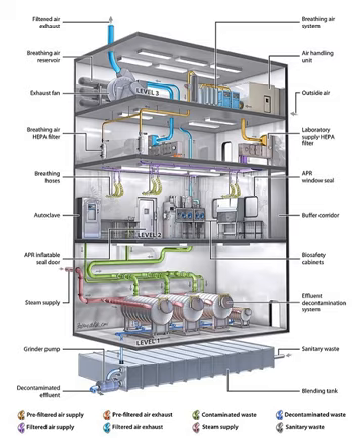In addition, the facility which houses the BSL-3 laboratory must have certain features to ensure appropriate containment. The entrance to the laboratory must be separated from areas of the building with unrestricted traffic flow. Additionally, the laboratory must be behind two sets of self-closing doors to reduce the risk of aerosols escaping. The construction of the laboratory is such that it can be easily cleaned. Carpets are not permitted, and any seams in the floors, walls, and ceilings are sealed to allow for easy cleaning and decontamination. Additionally, windows must be sealed, and a ventilation system installed which forces air to flow from the clean areas of the lab to the areas where infectious agents are handled. Air from the laboratory must be filtered before it can be exhausted.